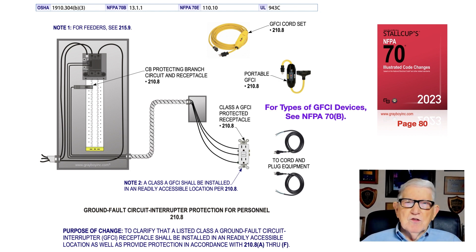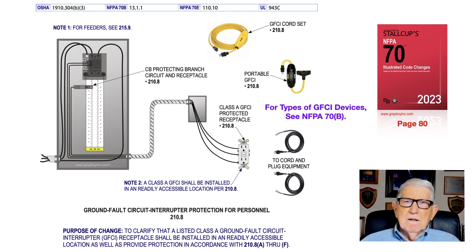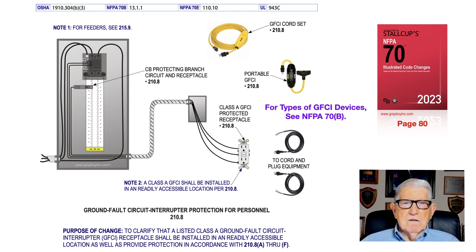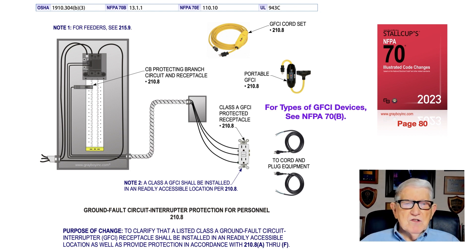As illustrated, you could have a circuit breaker that provides GFCI protection, AFCI protection, short circuit, ground fault, and overload protection all on one breaker. Or you could have a cord set with a GFCI protective device installed within it, a portable type GFCI, or a GFCI receptacle itself.